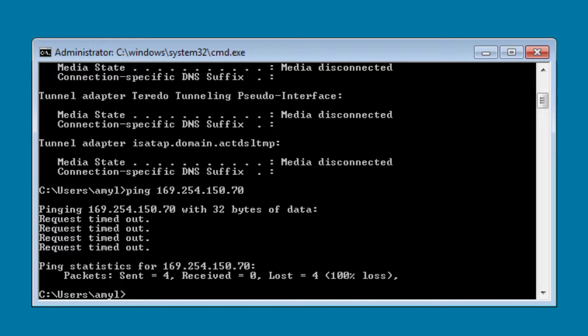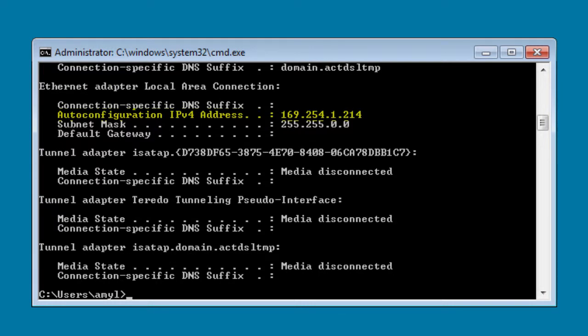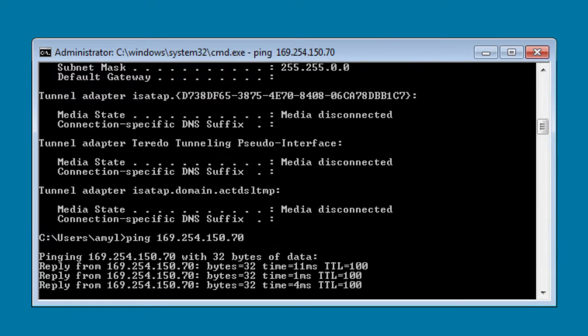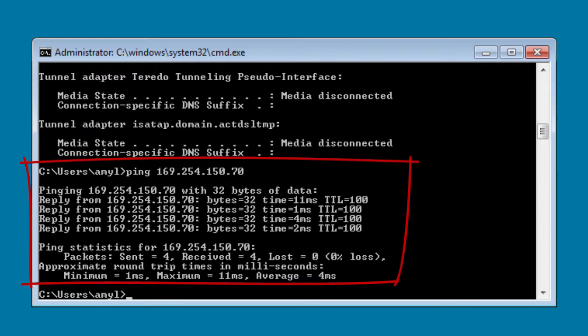I am going to go back to my command prompt. Now when you make these types of changes, they do not happen instantaneously. I'm going to type in ipconfig and see what my computer says. In this case, my computer has very quickly adjusted its IP address — it is now back to a 169.254 format, which should successfully communicate with the fire alarm control panel. I can try pinging the panel by typing PING followed by the IP address of the fire alarm control panel, and again I am getting a reply. So now I know I can successfully communicate again with the fire alarm control panel.